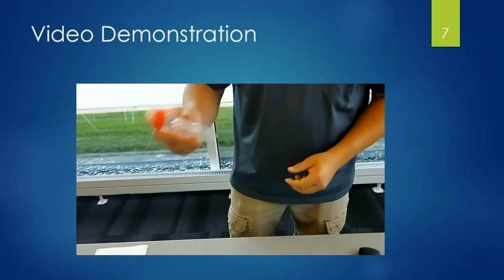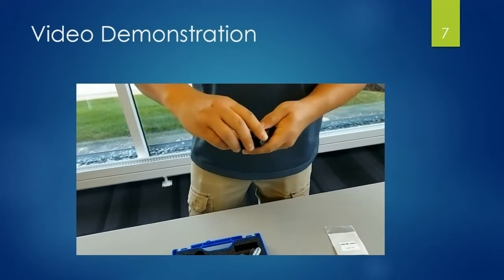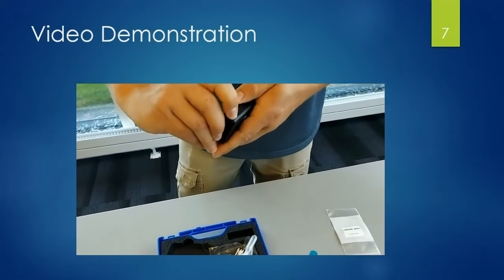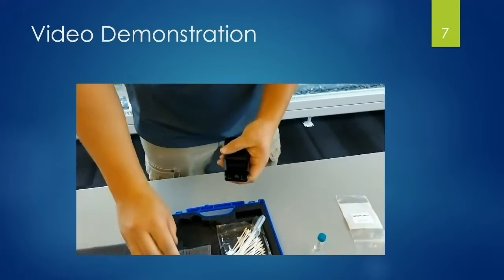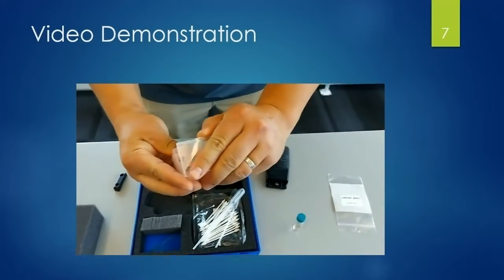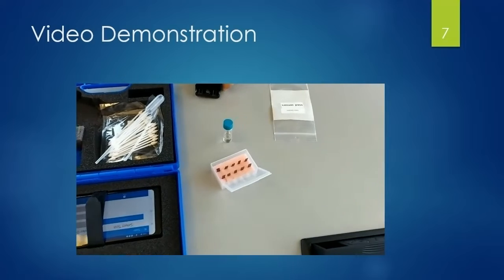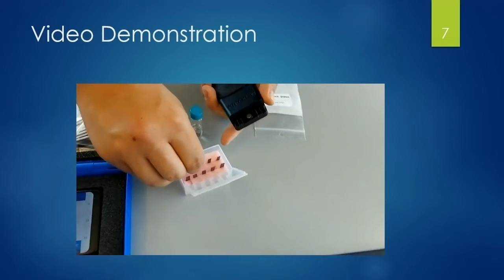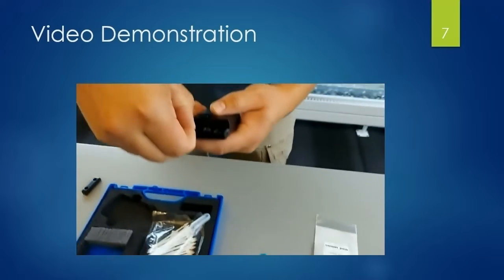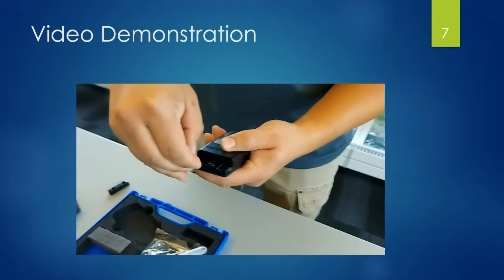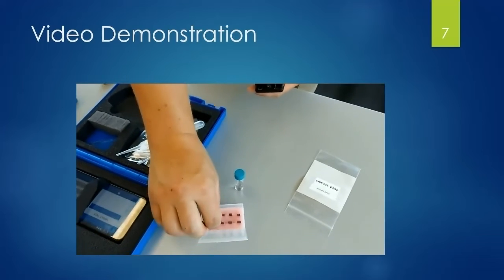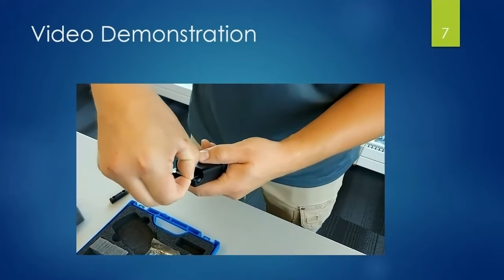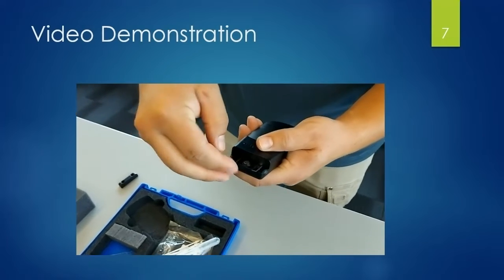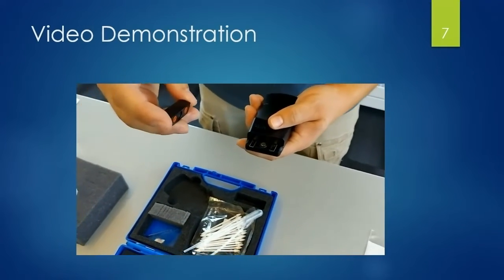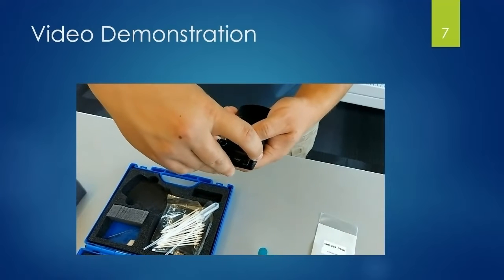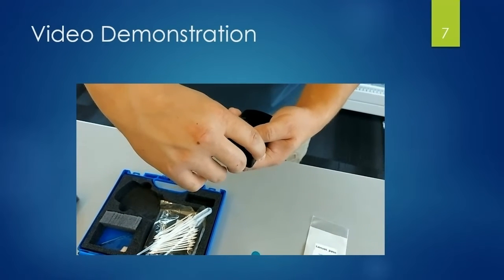After mixing thoroughly and waiting the appropriate amount of time, you can begin your analysis. Remove the cap, which is held in place by a magnet. Grab one of the sensors, careful to grab only by the blue silicon substrate, and avoid handling the gold sections as much as possible. Insert them into the sensor. Make sure that you have a good connection. Return the cap, which ensures it has a watertight seal and that your water sample is only exposed to the active area of the sensors.